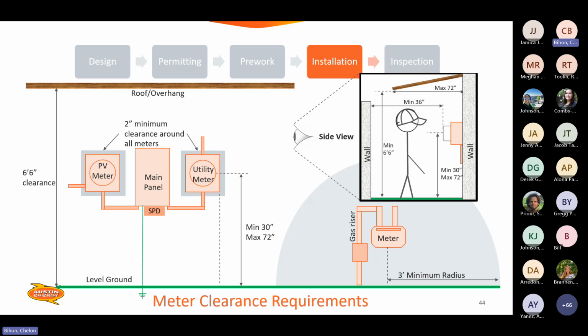You got the headroom, you see there, a minimum of 6'6". And you got your clearance, a minimum of 36 inches. That ground must be flat to walk on. If you look at the overhang, it's a maximum of 72 inches over top of that, no more than that. And we are maintaining a 3-foot minimum radius around the gas regulator meter.